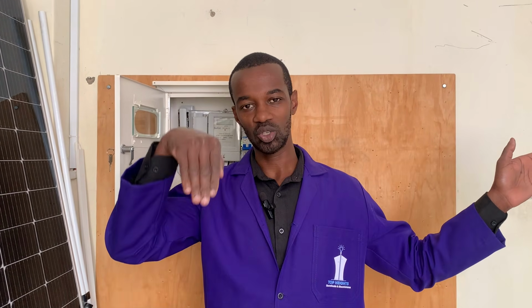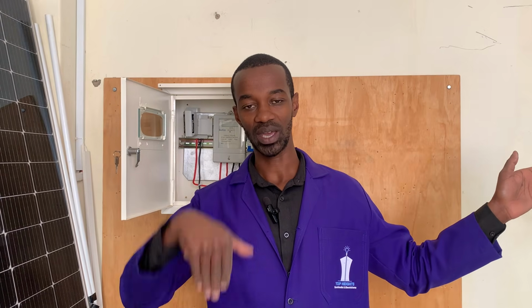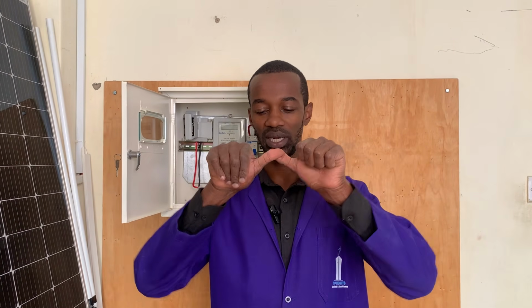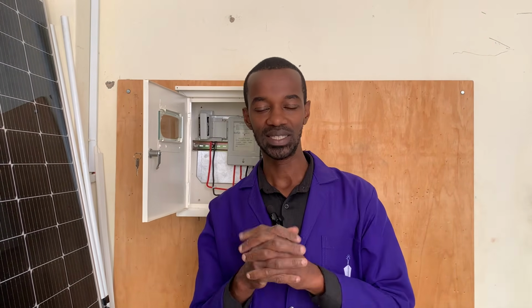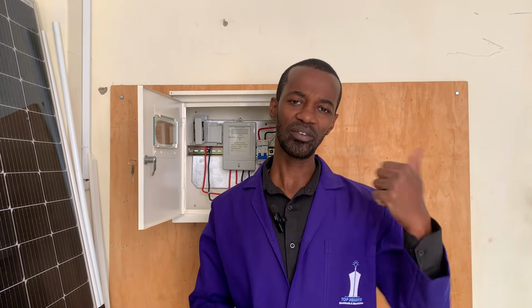What is going to the consumer unit and what is coming from the earth rod or earth pit are bonded at the meter box, and that is how the earthing is done. In the previous video I did, I bonded the earthing and the neutral at the meter box. With today's metering system, you cannot do that, because that will definitely be a mistake, leading to what is referred to as a bypass error. This will charge the customer a lot of power bills upon their normal house consumption.